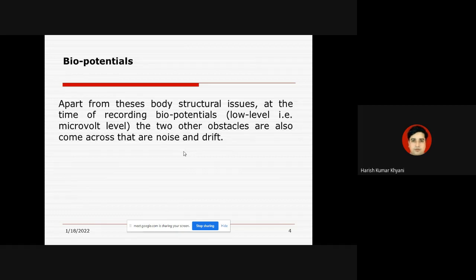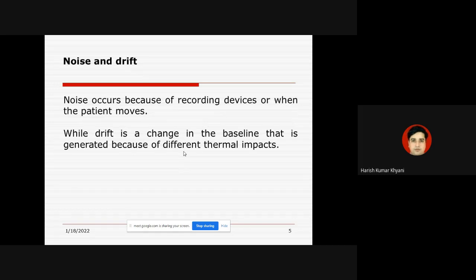Apart from these body structural issues like skin cover, bones, and body fluids, at the time of recording these biopotentials — which are at very low level, usually at the microvolt level — there are two other obstacles: noise and drift. Noise occurs because of recording devices, patient movement, or talking during recording. Drift is a change in the baseline generated because of different thermal impacts.